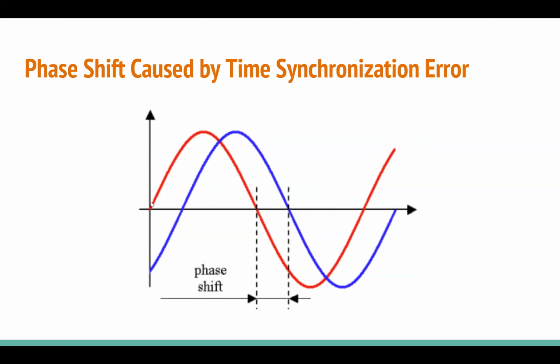So if relay A thinks this is the current and relay B thinks this is the current, we have this phase shift between them. And you can see that gives a differential value when we're subtracting them at any certain point in time. So the time error can be a certain amount. That's basically that 1 microsecond. So if we're looking at a waveform like this, in terms of power on the United States power grid, it runs at 60 hertz. So that would be 16.66 milliseconds per cycle. So one full cycle of the power or the signal here would be 16.66 milliseconds. We're saying that can't be offset by more than 1 microsecond in either direction to compare it against this other one. So it'd be a very, very tiny fraction of this that it's allowed to be offset.